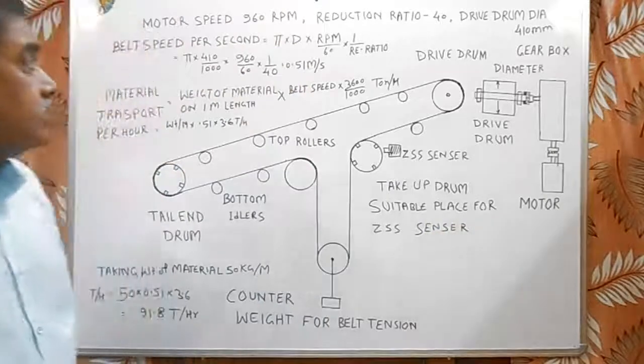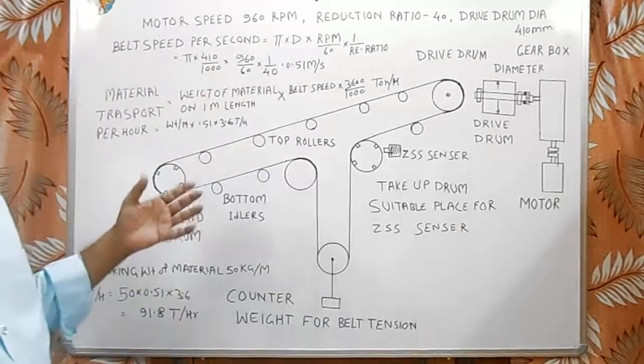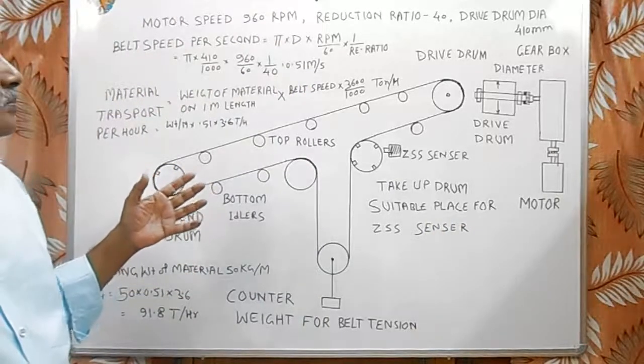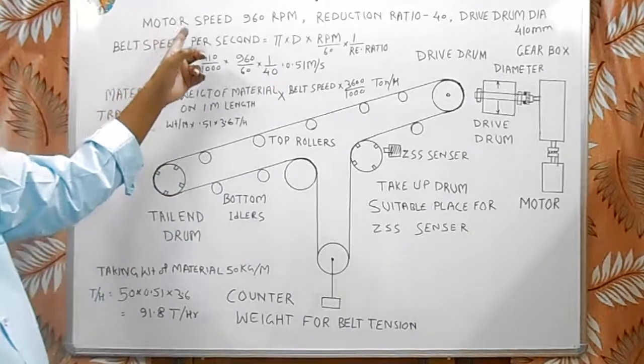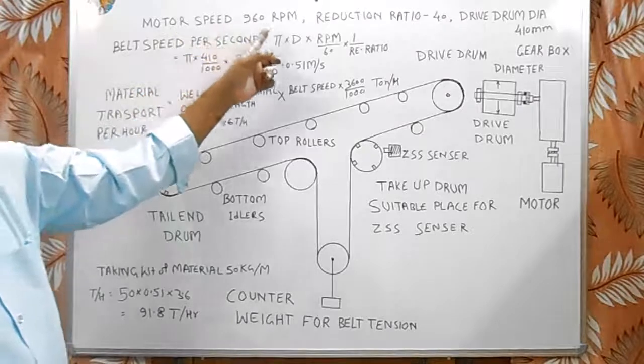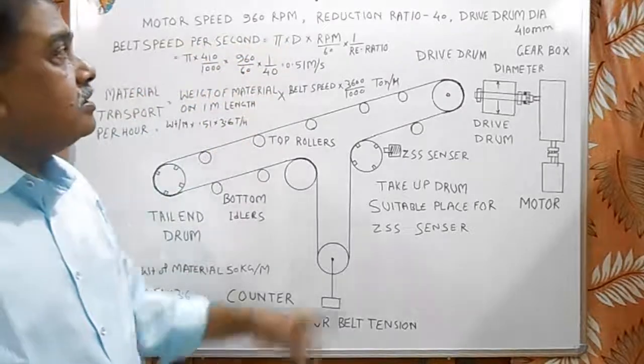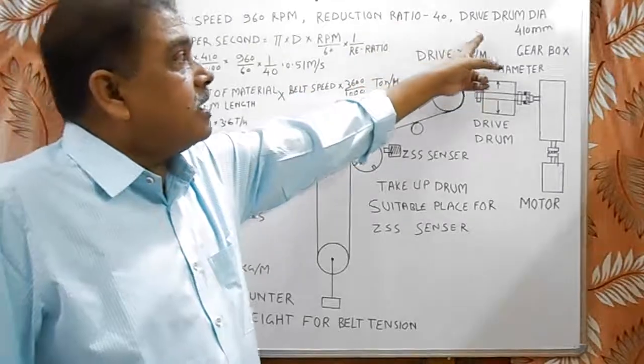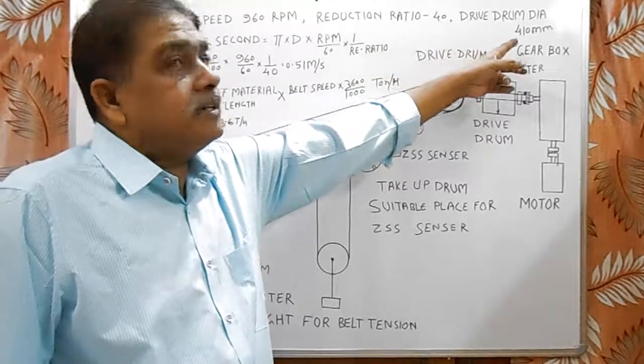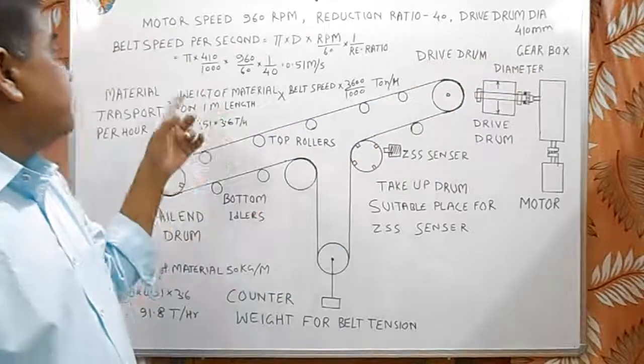For calculation of material handling per ton per hour, we need to have these things. First one motor speed that is 960 rpm in this case. Reduction ratio of gearbox that is 40. And drive drum diameter here it is 410 millimeters.